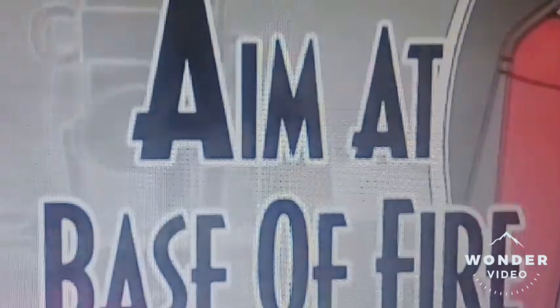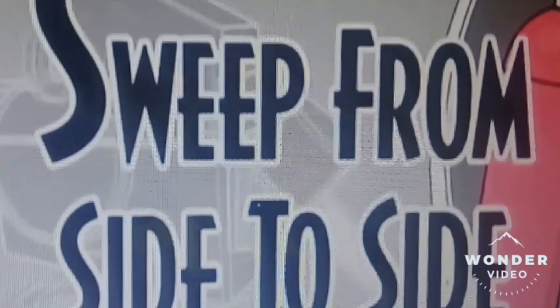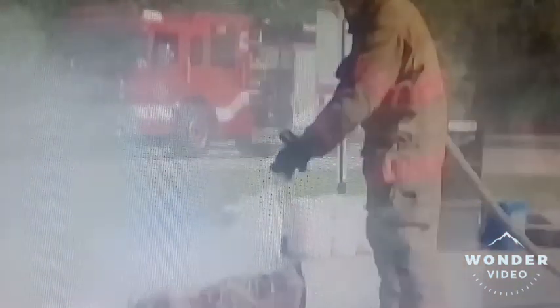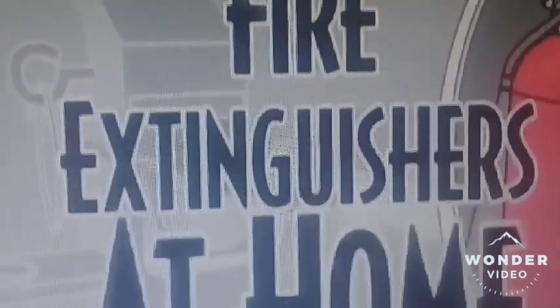A. Aim the fire extinguisher nozzle at the base of the fire. S. Squeeze the lever that operates the handle of the fire extinguisher. The extinguishing agent will immediately begin to discharge. S. Sweep from side to side until the fire is completely put out. Even when the fire is put out, keep an eye on it until the fire department arrives. Remember that every fire extinguisher should be maintained every 6 months to ensure maximum effectiveness.